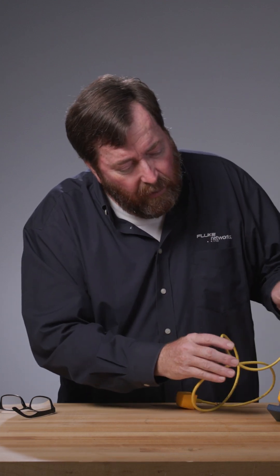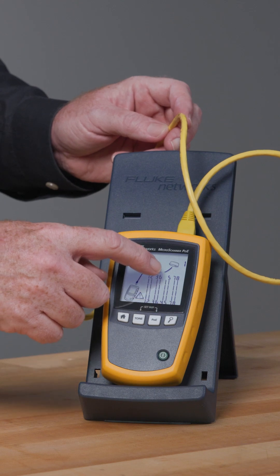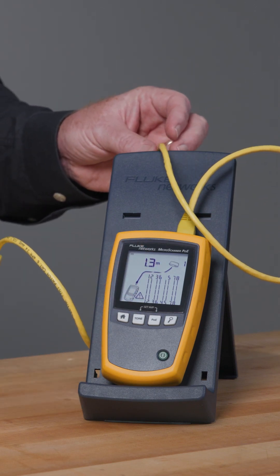So I'm going to use the — well, I'd like to call this a terminator, but the technical term for it is the hat. I'm going to plug this hat in, and it's going to tell us — look at that — conductor number four doesn't go all the way up to the top. One of the conductors is open.